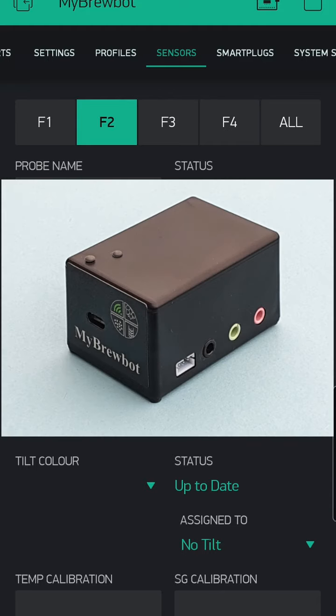4 probes attached to a hub on the black jack socket, and 4 probes attached to a hub on the green jack socket. The pink jack socket is for a pressure sensor only. Do not plug a probe or hub into the pink socket. 2 probes can be attached directly to the controller through the black and green sockets.